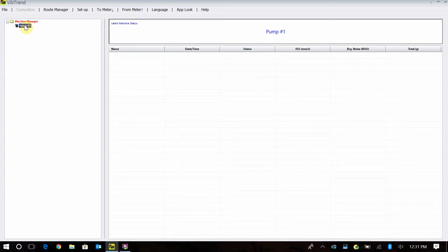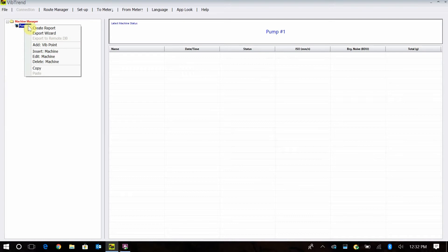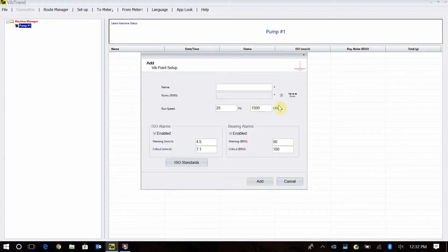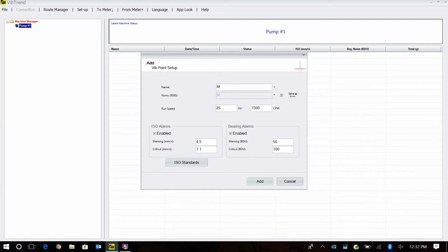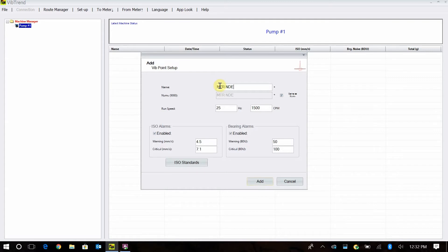The next thing we would add are our vibration points below pump number one. On your pump, you're going to have your motor non-drive end, motor drive end, pump drive end, pump non-drive end. I'm going to right click here and add my first vibration point. Simply tell it to add. This is where I give it the name, and this is what shows up on the 9080 vibration meter when you're collecting data. We're going to type in MTR for motor and then NDE for non-drive end. We're going to start at the back of the motor and work our way to the front and then to the pump. After you put that in, we have to put the speed of the motor in. I'm going to put in 1800 RPM because that's what this pump is going to be turning.